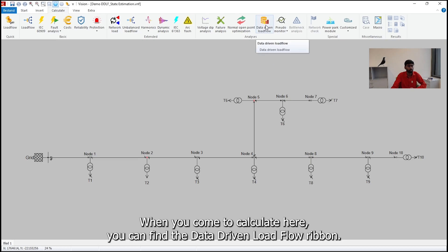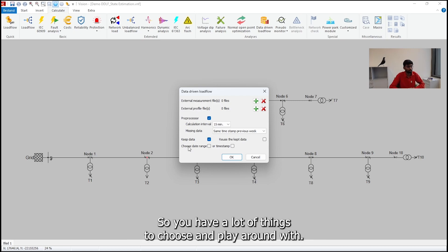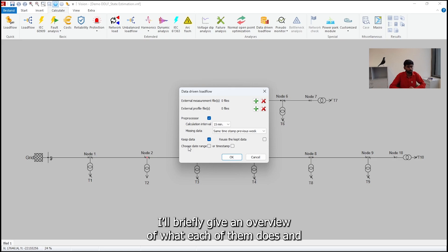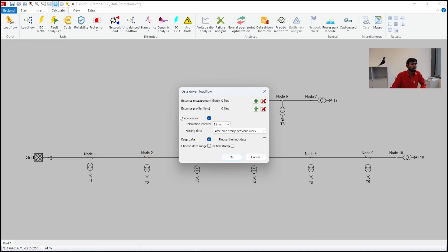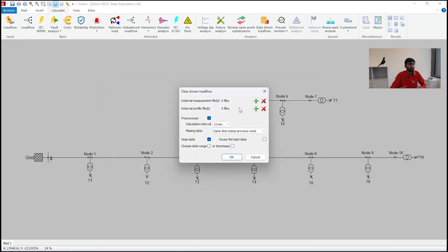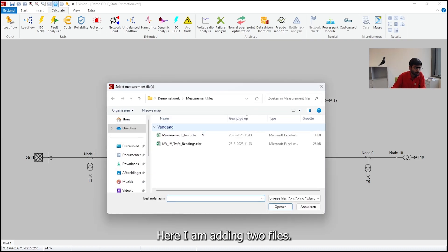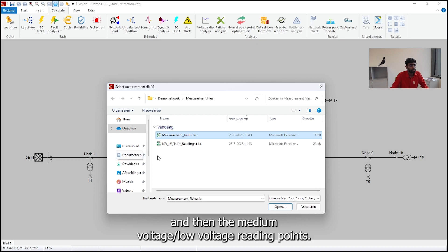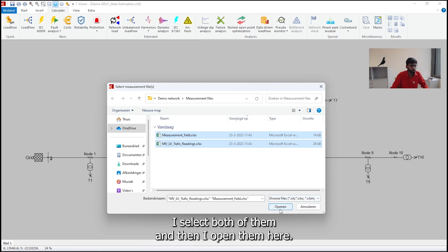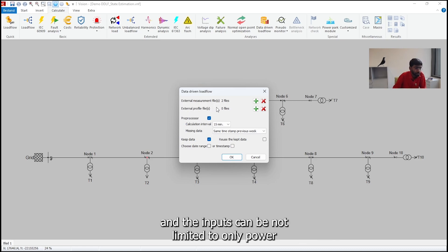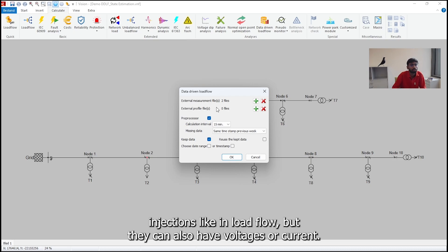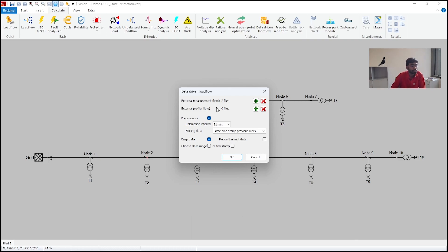Then you can see that when you come to calculate here, you can find the data driven load flow ribbon. You can just go inside the ribbon and you can find multiple options here. You have a lot of things to choose and play around with. I'll briefly give an overview of what each of them does. The external measurement files is basically to add the files that you want. So here, I'm adding two files. The measurement field, which refers to this point here, the distribution automation point, and then the medium voltage low voltage readings point which corresponds to the transformer loads. So I select both of them and then I open them here. So basically, now I already have two things here and the inputs can be not limited to only power injections like in load flow, but they can also have voltages or currents or anything that can be useful here for state estimation.